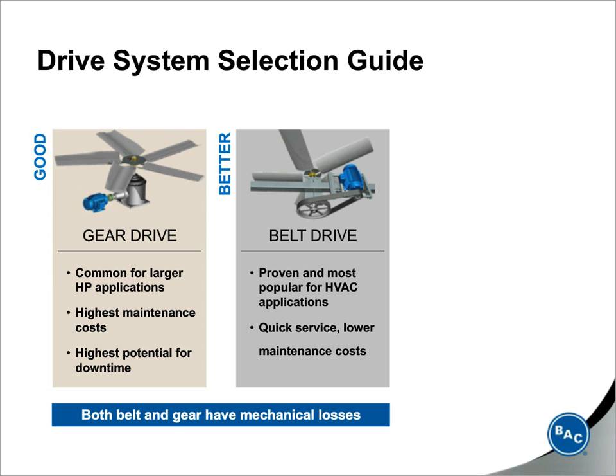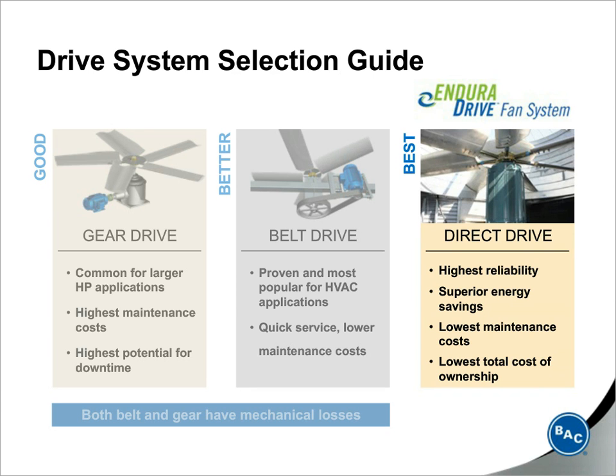So even though belt does offer a lower total cost of ownership than gear, with both belt and gear there are still mechanical components. They're moving components, moving at varying speeds, and they're going to degrade over time. This degradation is going to introduce mechanical losses into the drive system. So that's where direct drive technology comes in and really shines. Previously, there have been challenges to using direct drive motors in cooling towers, particularly on larger cooling towers. With slower operating speeds, direct drive motors require much greater torque than induction motors that typically operate at about 1,800 RPM. In the past, this really limited direct drive to motors at about 15 horsepower and smaller, which can be small for cooling towers.